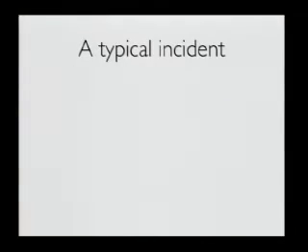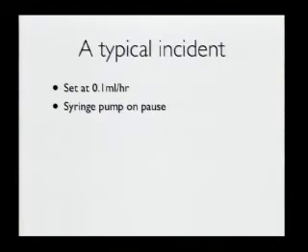Here's a typical incident which happened, I think, in Belfast Hospital. A doctor and a nurse were dealing with a premature baby connected to an infusion pump. And the infusion pump was set at 0.1 mils per hour, delivering stuff to the baby. The pump was in fact set on pause, so it had been set up to deliver this amount, but it wasn't delivering that amount.